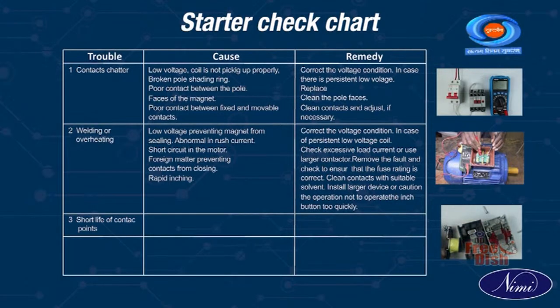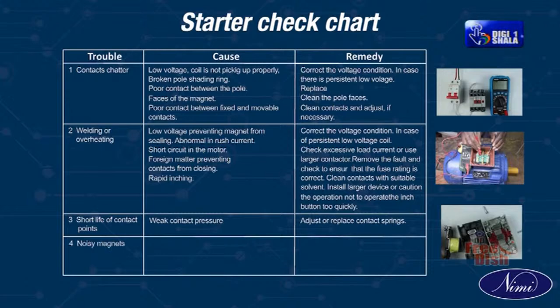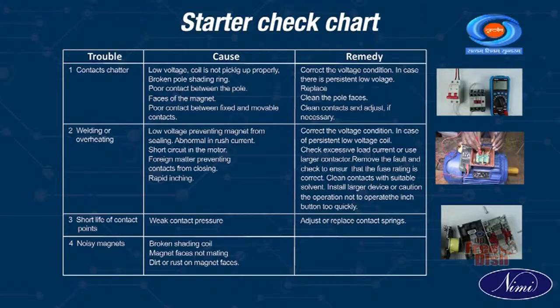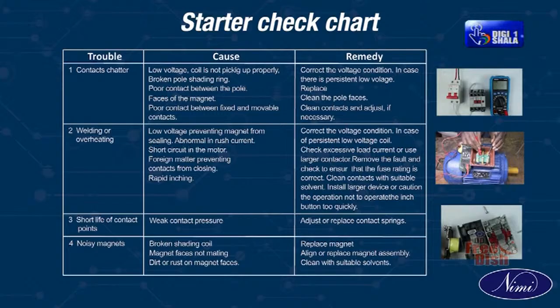Trouble. 3. Short life of contact points. Cause. Weak contact pressure. Remedy. Adjust or replace contact springs. Trouble. 4. Noisy magnets. Cause. Broken shading coil, magnet faces not mating, dirt or rust on magnet faces. Remedy. Replace magnet, align or replace magnet assembly, clean with suitable solvents.